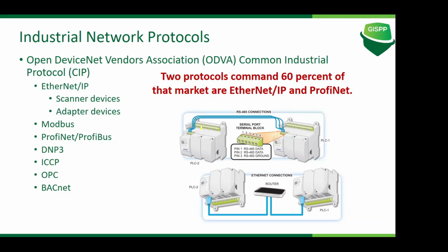DNP3, Distributed Network Protocol 3, is basically a public industrial communication protocol. It was also developed for SCADA master servers. Mostly its implementation is between SCADA masters, the servers where SCADA is installed, which we call SCADA servers, and interaction with the PLCs or the IEDs in electrical grid system environments. Mostly because it has its roots with NERC, an authority in the US working on power grid OT security. They are kind of a regulator there, so they prefer this DNP3 standard, where SCADA master servers need to talk with the IEDs.